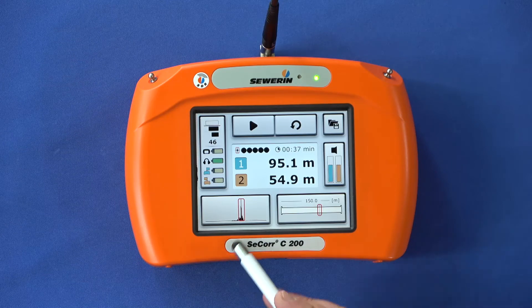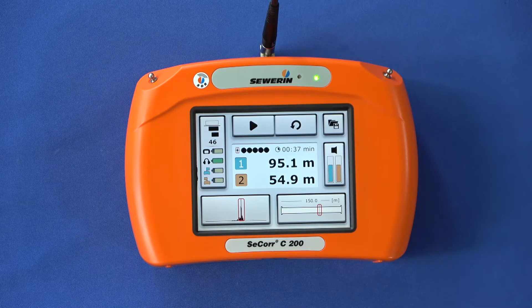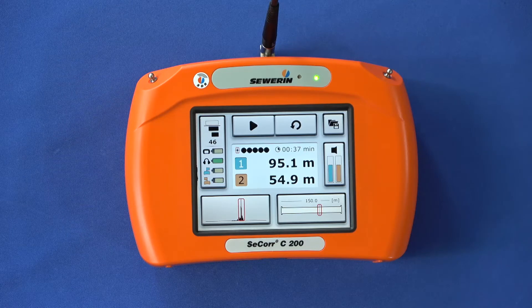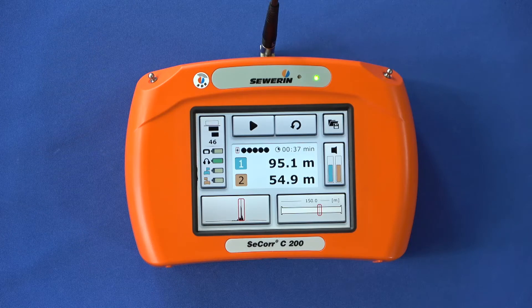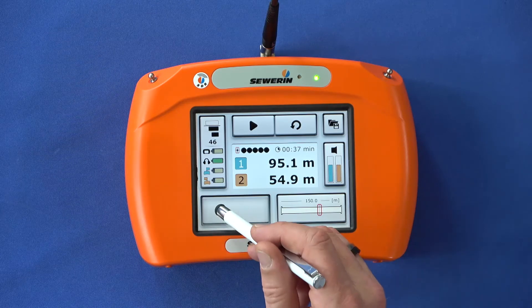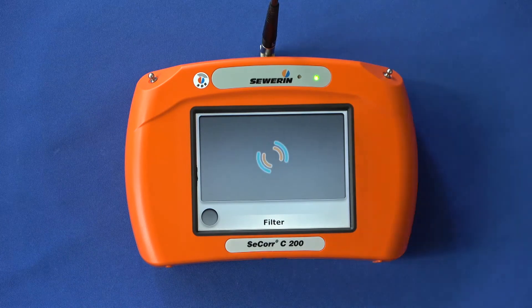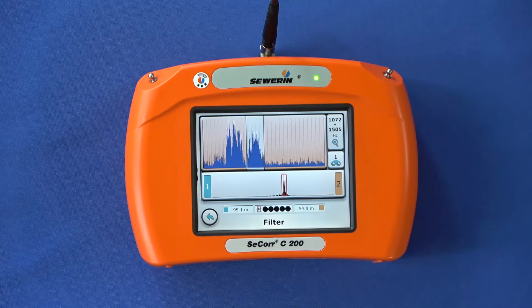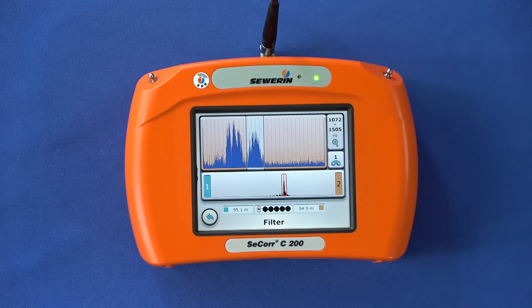In the lower left area of the display you will see the filter button. You can use this function to reach all detailed dialogs that help you optimize the result. During each measurement the C200 regularly calculates optimal filters for the respective noise situation. If you switch to the filter dialog, the system provides you with two automatically calculated optimal filters as a suggestion. Tap the button to open the filters dialog. In the upper half of the dialog you can now see the filter base. Various functions are available as a basis for the selection of useful filters, which you can select in the settings. We recommend the coherence function as the factory setting.